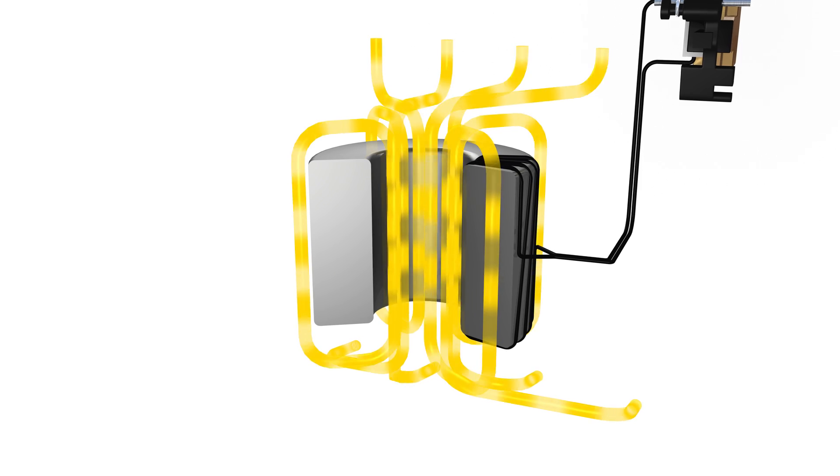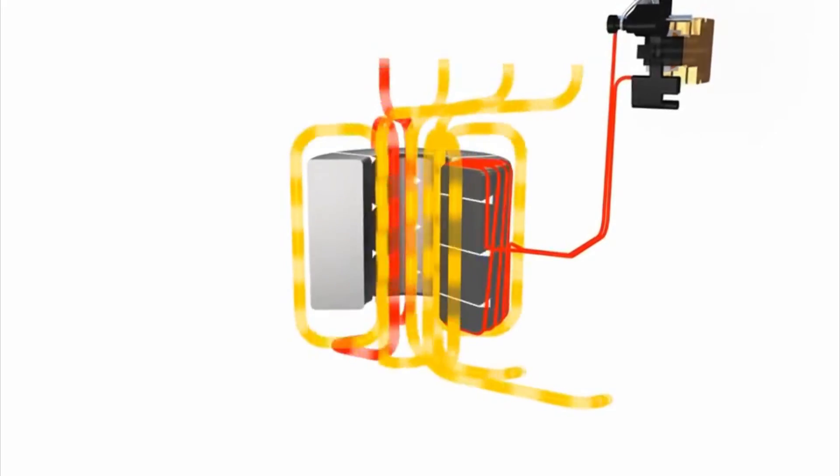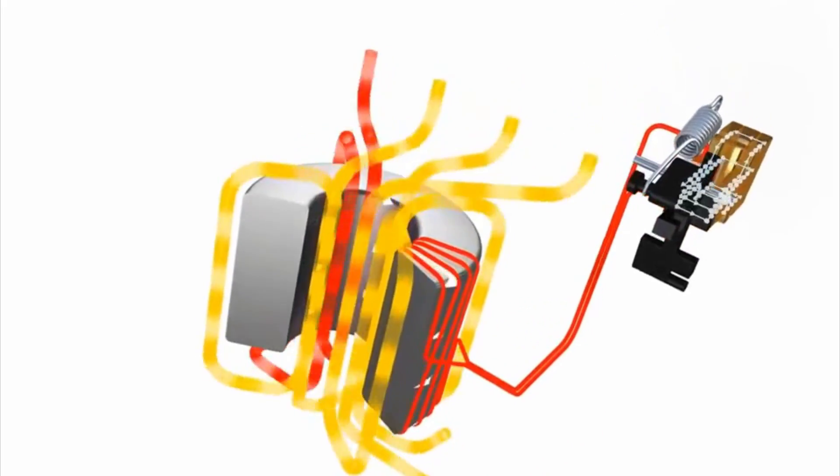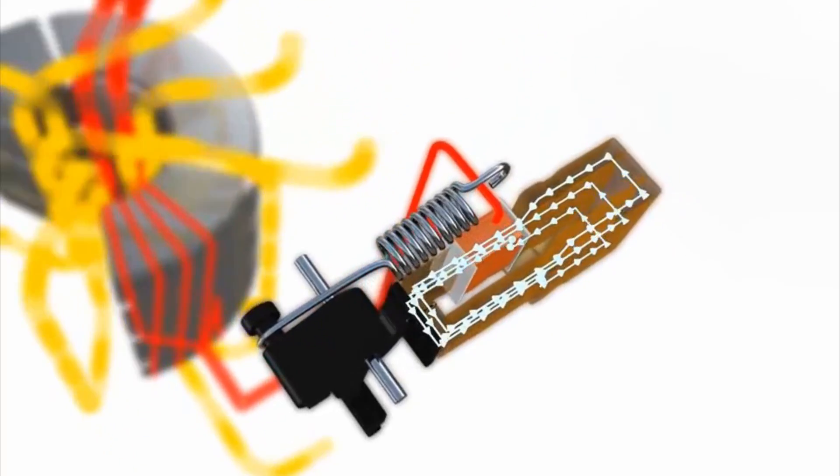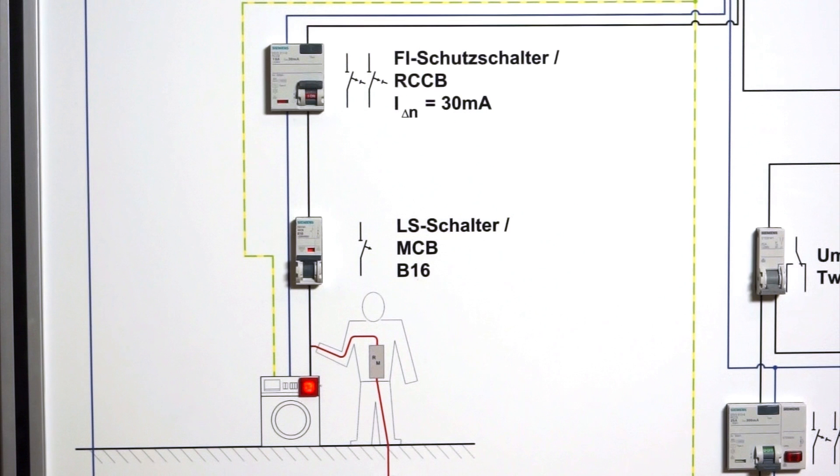A fault current flowing due to an insulation fault will generate a magnetic flux in the transformer, which will in turn induce a voltage in the secondary winding. This mechanism acts upon the holding magnet relay and releases the RCCB in case of limit value exceedance.